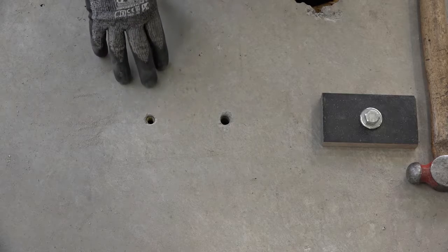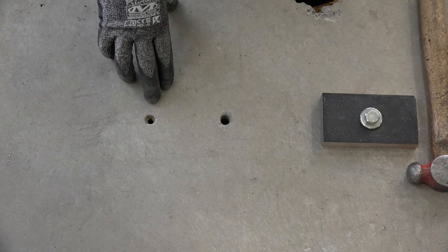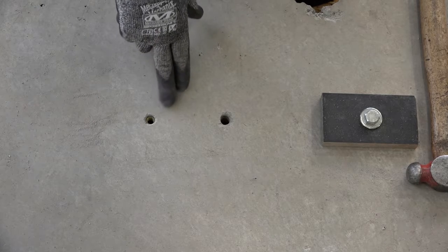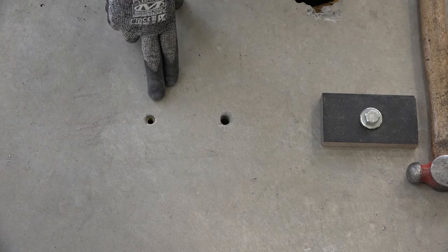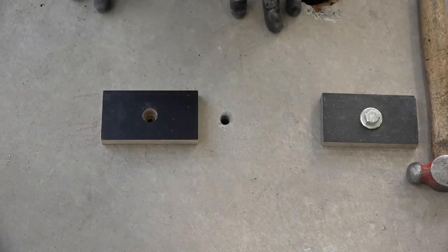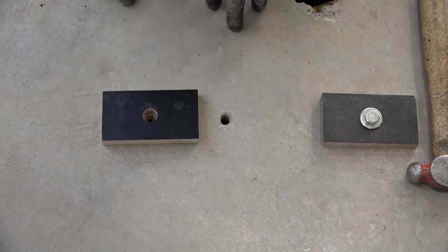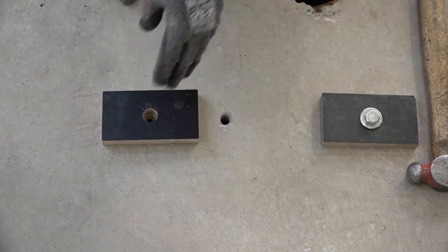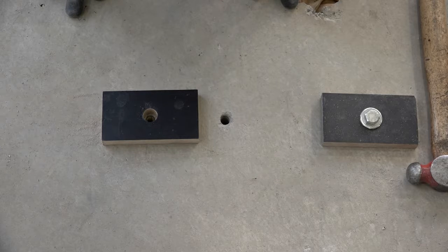So unlike the torque-controlled expansion anchors, this anchor is now set independent of any torque that we apply to the bolt being placed into the insert. All that's left to do is place the fixture, get the appropriate bolt, and install the bolt in accordance with the specification.